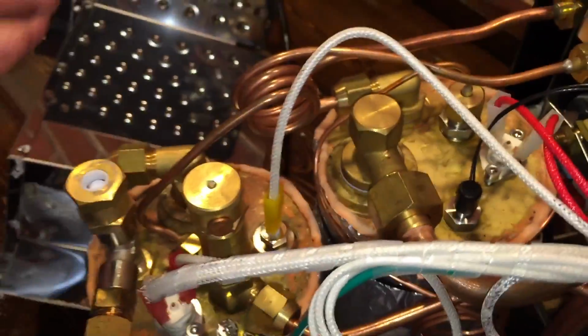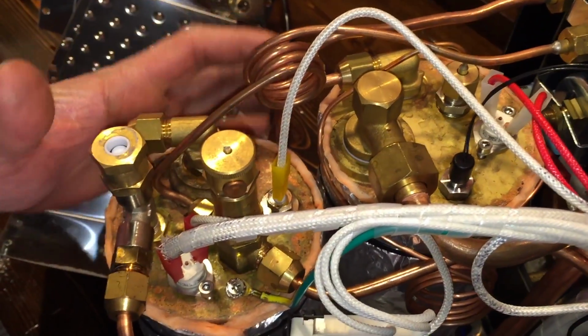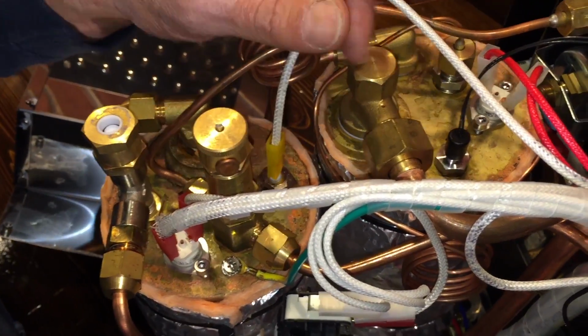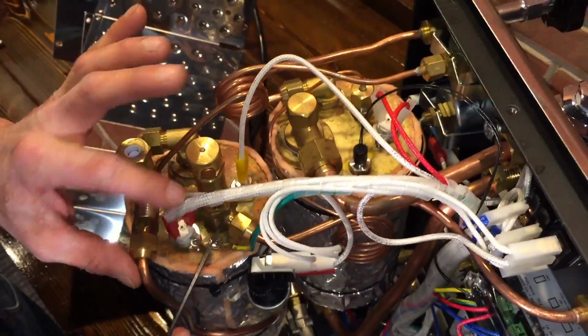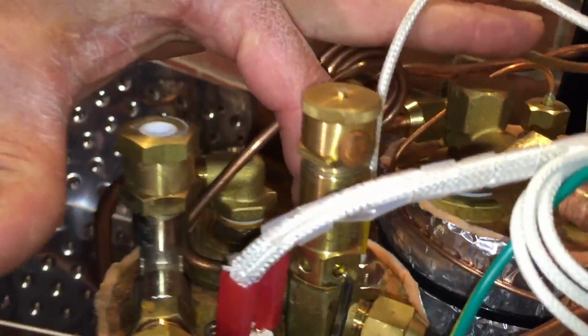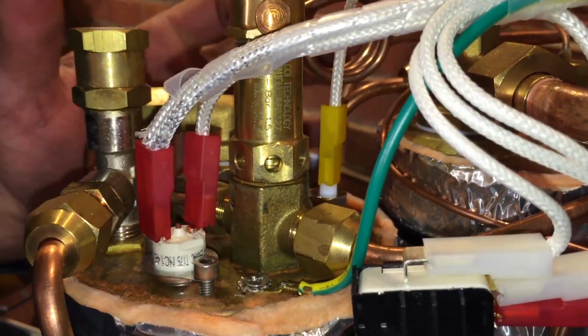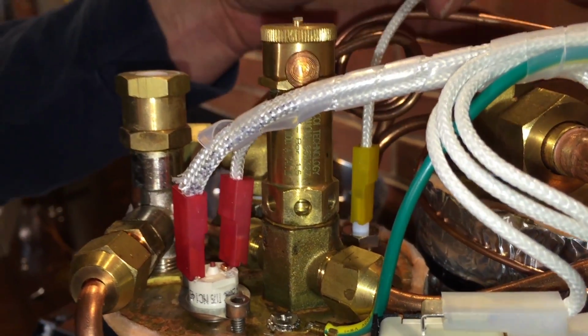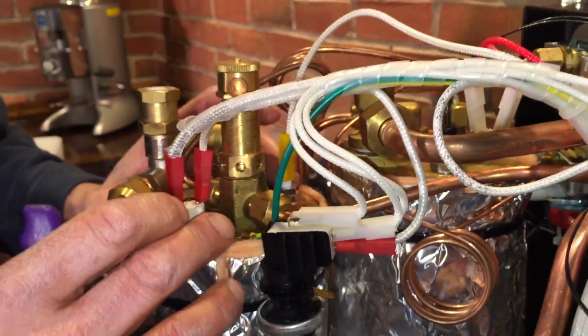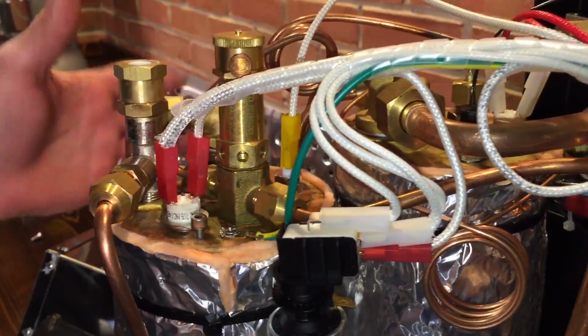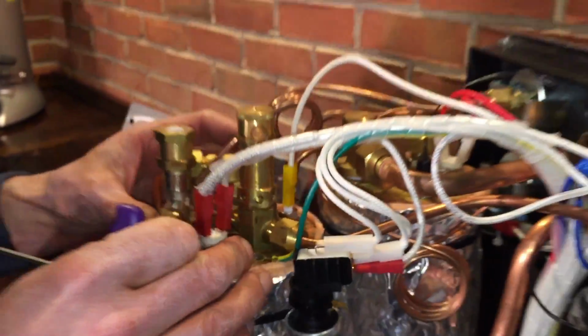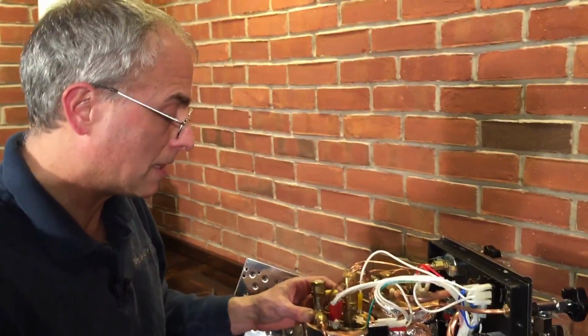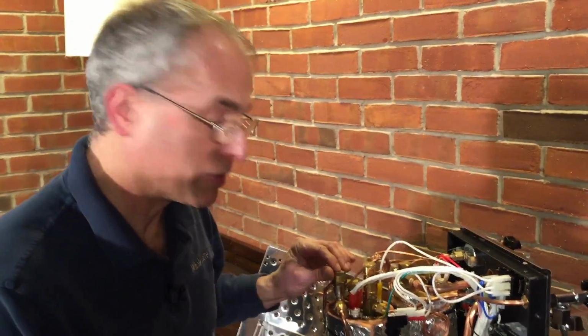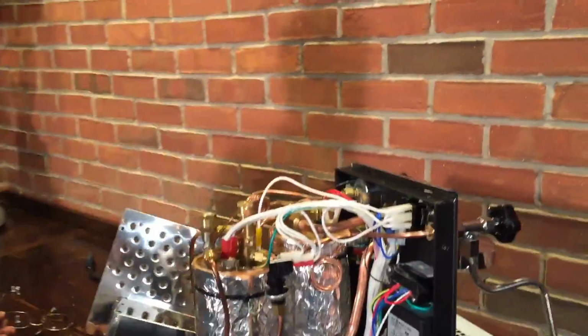Everything's fine. Usually, if it is acting up and this is the problem, let's say the wire is disconnected, the pump will be on and water will be squirting out all over this right here. If that happens, you're going to want to obviously turn the machine off, and after you reconnect the wires, make sure everything's dry. Maybe let it sit for a day, maybe even use a hair dryer to dry some of this off. It really shouldn't damage anything, but it'd be good to just make sure it's dry. And then put the machine back together.